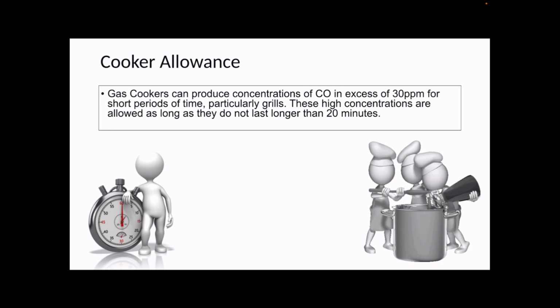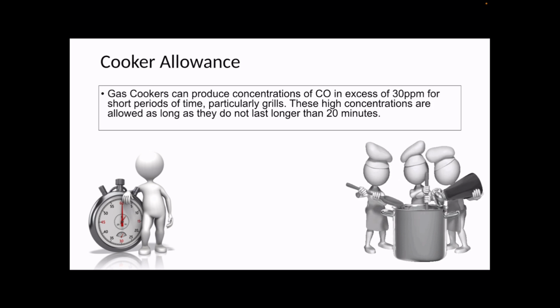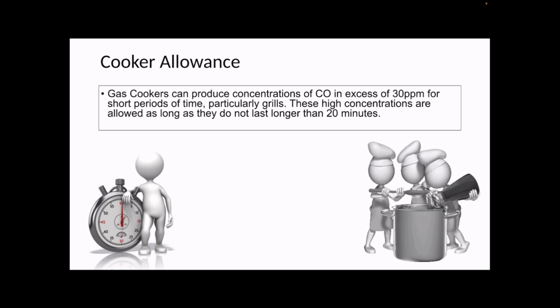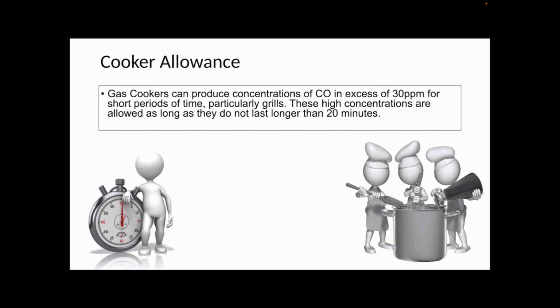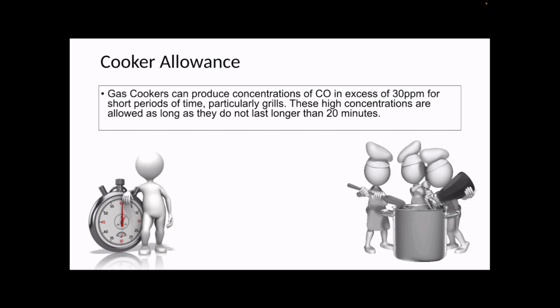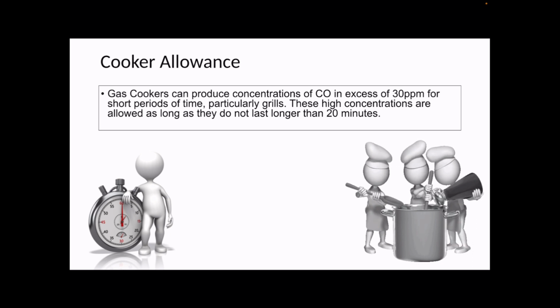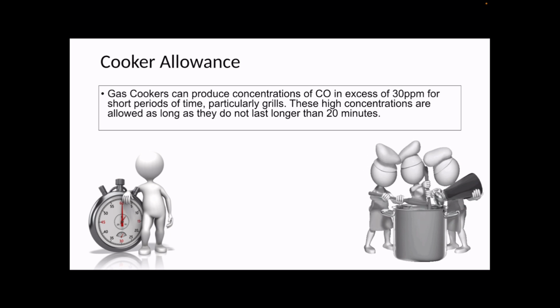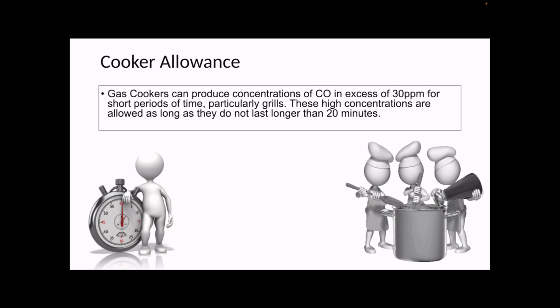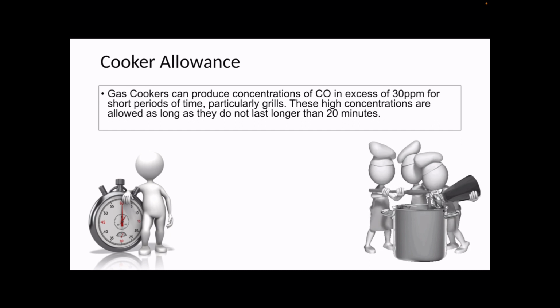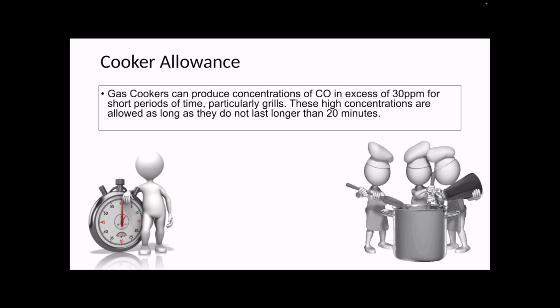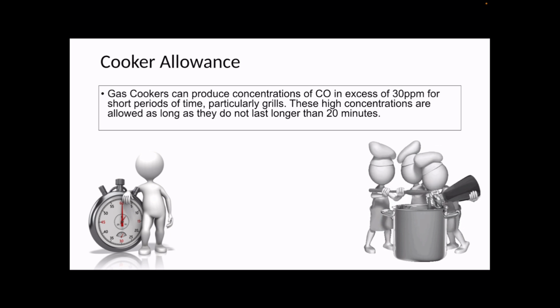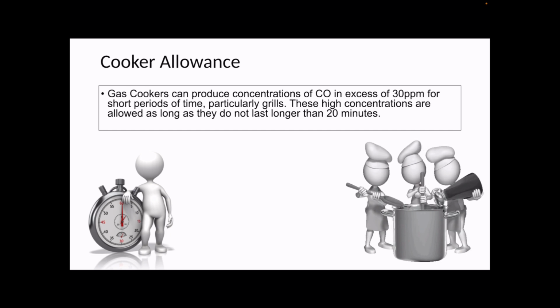Now with cookers, they can produce concentrations of carbon monoxide in excess of 30 parts per million for short periods of time. And in particular, the grills. We'll come on to grills later on because, of all the appliances you're going to deal with, they are the ones most likely to cause problems with your gas analysis. These high concentrations are allowed as long as they do not last longer than 20 minutes. This particular rule is well worth remembering for your exams and your assessment. The cooker allowance. They're allowed 30 parts per million for up to 20 minutes.